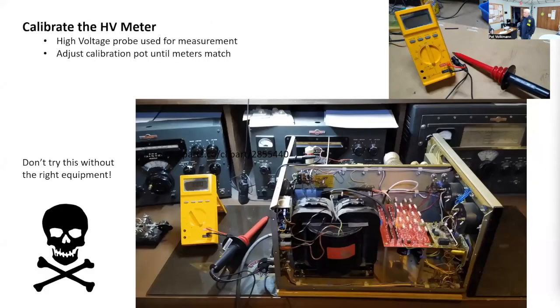The next step is to calibrate the high voltage meter. This has a panel meter that reads the power supply voltage, and this replacement power supply board has a potentiometer on it, so you can go in there and make adjustments to get it so that you read the correct value of voltage on the meter. But you have to be very careful doing this.